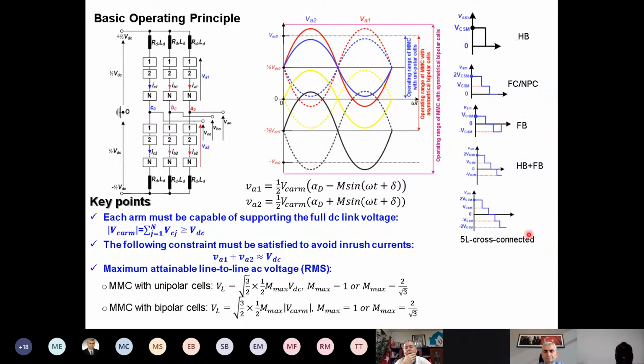And the implication of this type of cell you can see in the control range of the VSC. When we look at the top part here, between 0 and VDC nominal, this region from here to here is the control range of the MMC with unipolar cells, regardless of whether they are two-level or multi-level cells. So the half bridge and three-level cells, flying capacitor and neutral point clamp, the control range will be from here to here. And when we use a full bridge cell, which is a symmetrical bipolar cell, the control range can go from here to here. And also we can exceed the VDC.